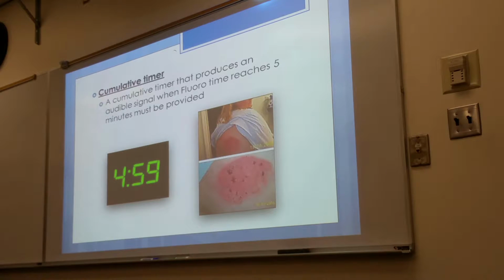Cumulative timer. When you're using fluoroscopy, a cumulative timer that produces an audible signal when fluoro time reaches 5 minutes must be provided.